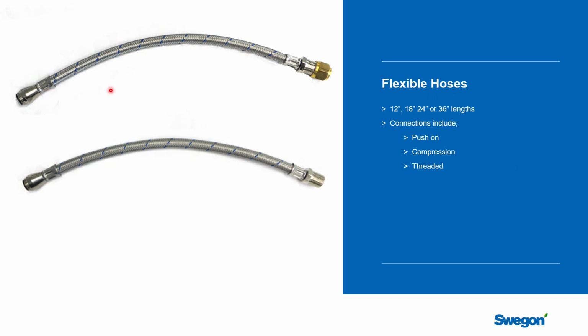A little bit about hoses and their connections. You can get them in all sorts of shapes and sizes. They're usually between 1/2 and 3/4 of an inch based on the flow rate required in the chill beam. Chill beam flow rates are quite low. They're usually between 1 and 2 GPM. And you can get them in different lengths, but typical lengths are in the 18 to 24 inches if you're in a ceiling plenum, and then 12 inches if you're doing something that's tight and there isn't a lot of space for excess hose.